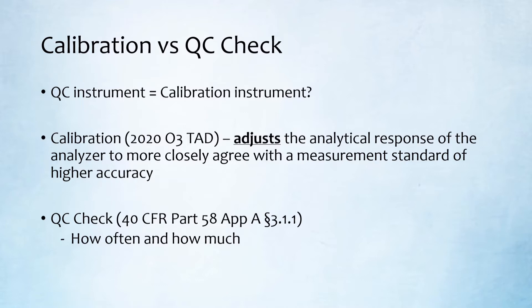In the 2020 Ozone TAD, the definition for calibration focuses on adjustment of the analyzer, which is really similar to the language in the QA handbook. Some monitoring organizations use the terms QC and calibration interchangeably and will use the same equipment for both QC checks and calibration. The 2020 Ozone TAD doesn't go into this, and the CFR and EPA aren't currently taking a stance on this issue, but CARB generally recommends the use of separate equipment for QC checks versus calibrations. You'll have to follow the guidelines outlined in whatever QAPP and SOPs your organization is following.